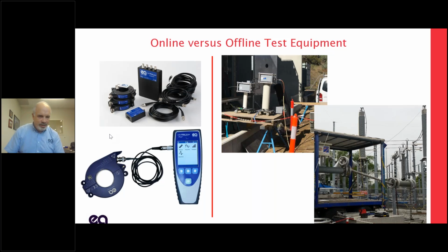On the left is some stuff, and arguably it's stuff by EA, but it's handheld online test equipment. We're testing at 60 hertz, which is good. We are testing at line voltage under normal operating conditions. We're testing with current flowing because current will cause things to increase. If you have a crack, that crack might expand with temperature.